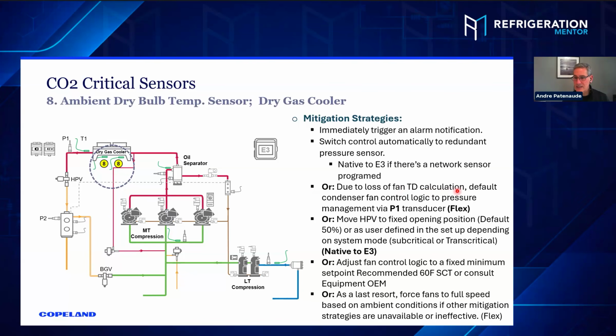due to that loss of TD calculation now, because you can't calculate TD because you've lost that sensor, you can default your condenser fan logic to pressure, to P1 management. So manage off of a P1 pressure. You can also move your high pressure valve again to a default opening. That's the same one we've showed before.